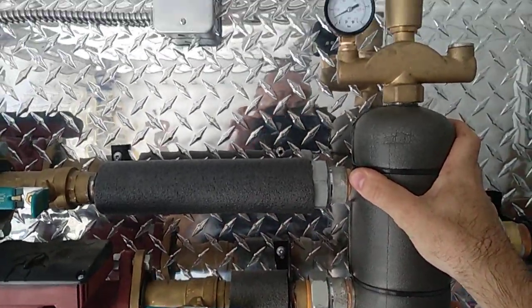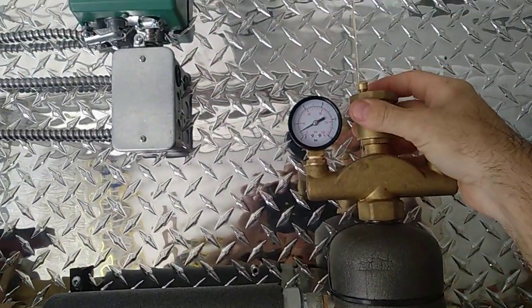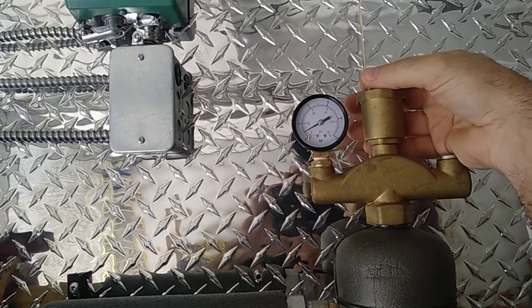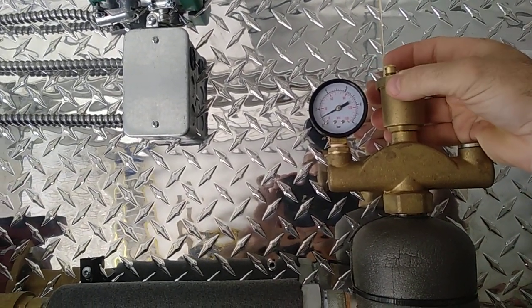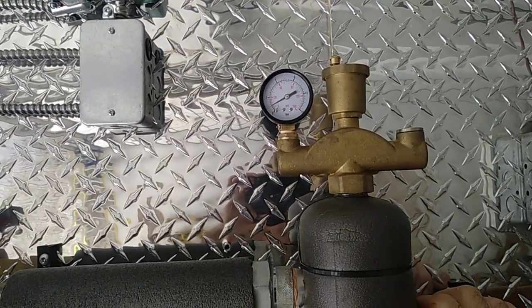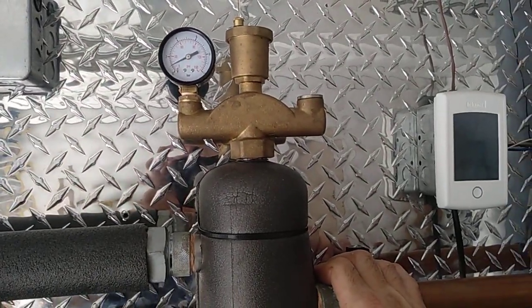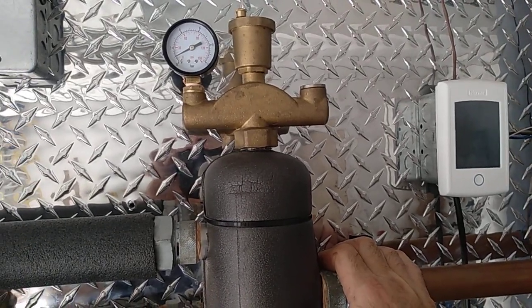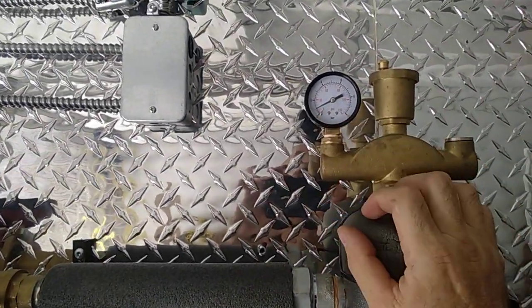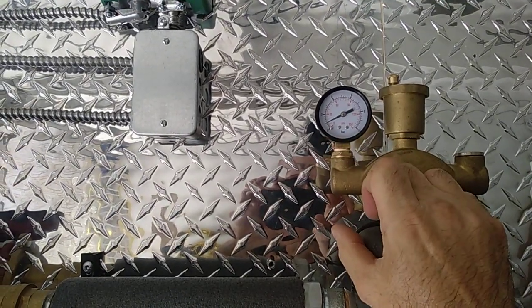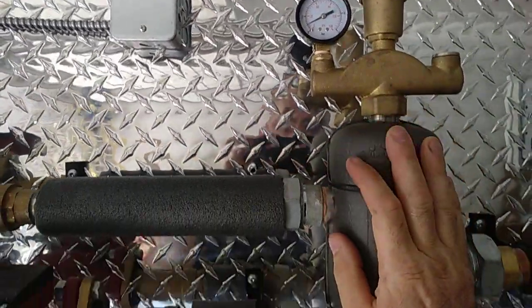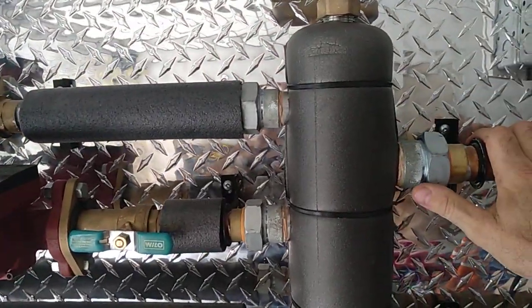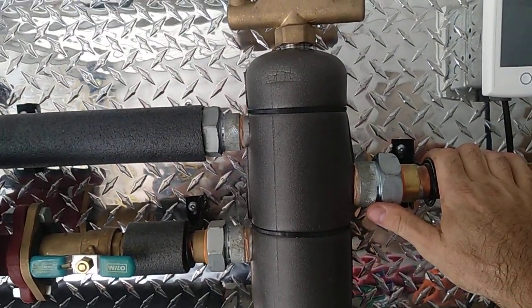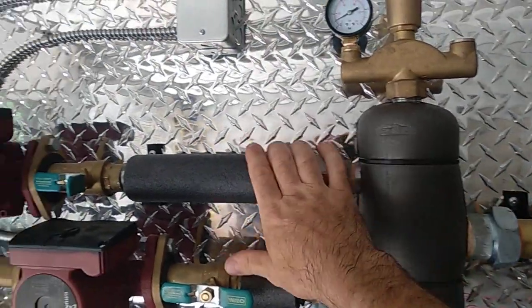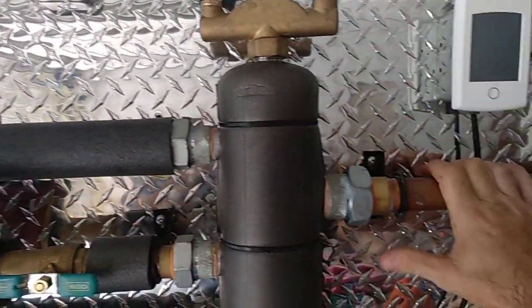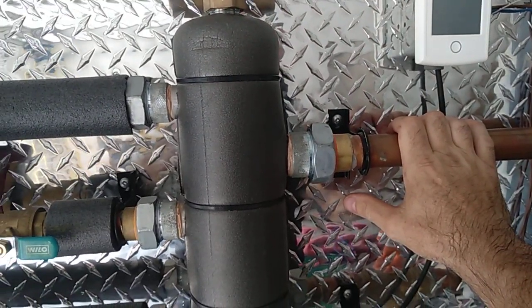Second function of this hydraulic separator is that it gets rid of the air. There's a little air vent on top of it, so any air trapped in the system that was not bled out will not keep circulating in the system and messing up the pumps. Also it has a little pressure gauge that shows us that the pressure is indeed 15 psi inside the system. Another function of this hydraulic separator is that it prevents thermal shock both for the concrete slab out there as well as the boiler's heat exchanger.